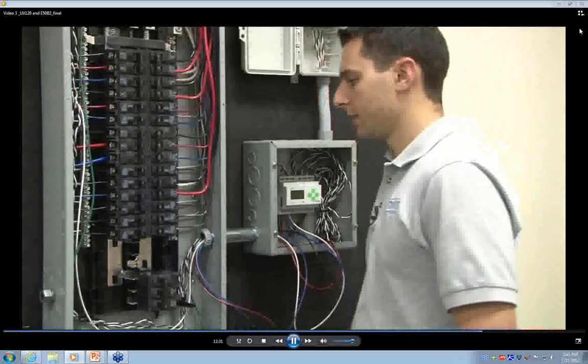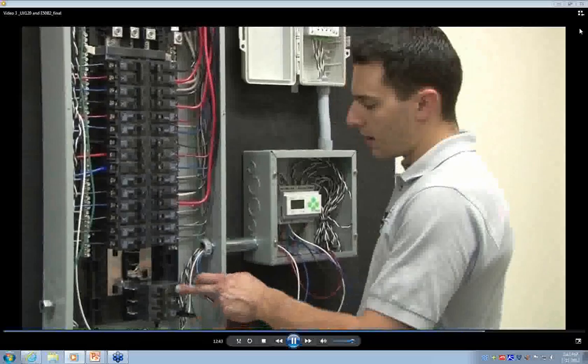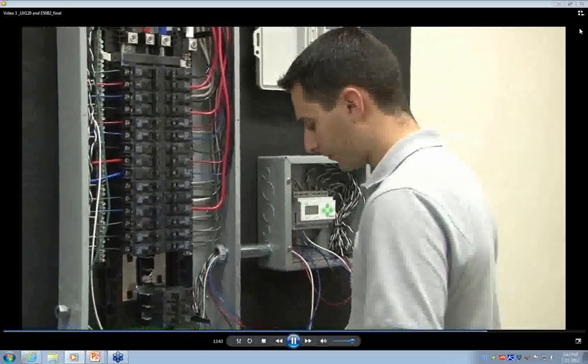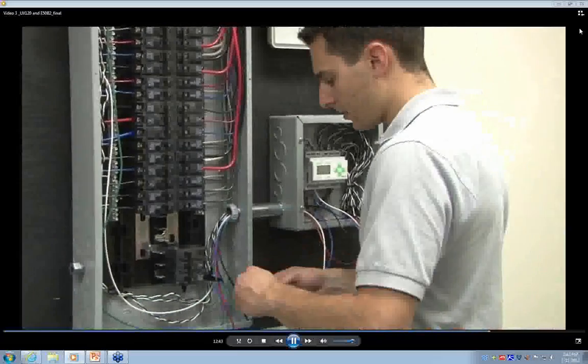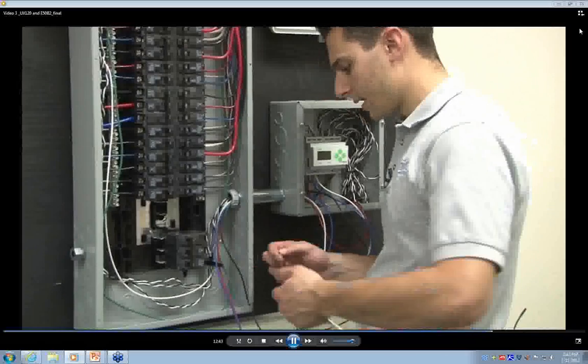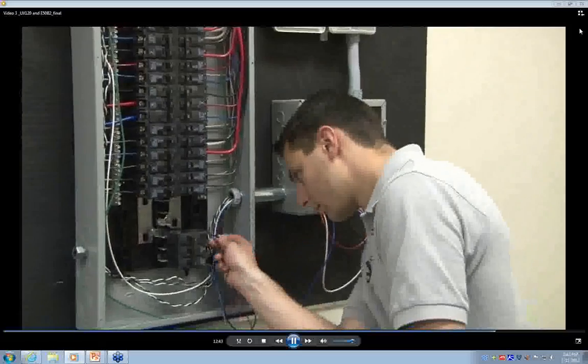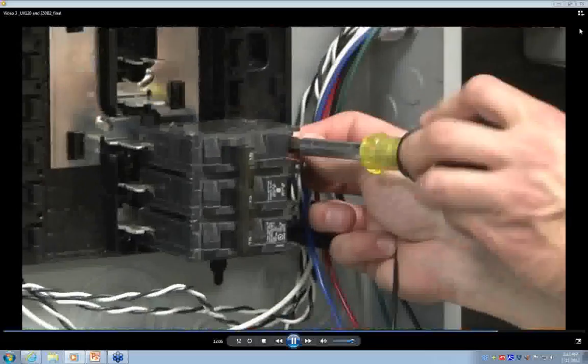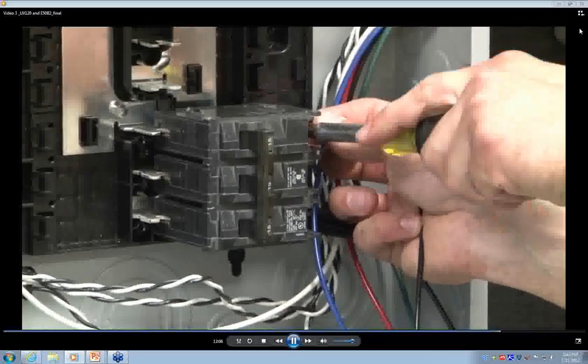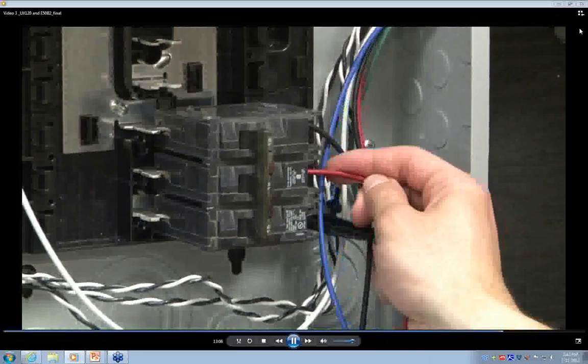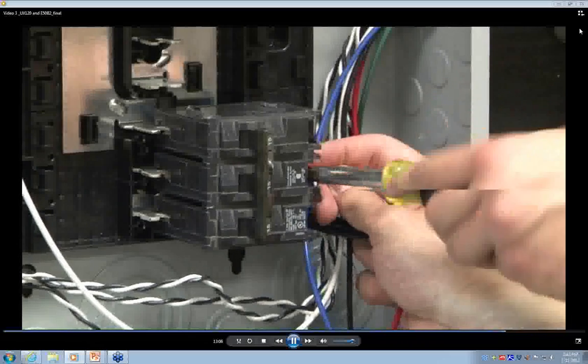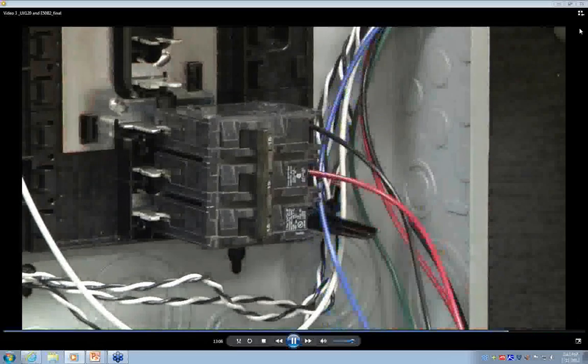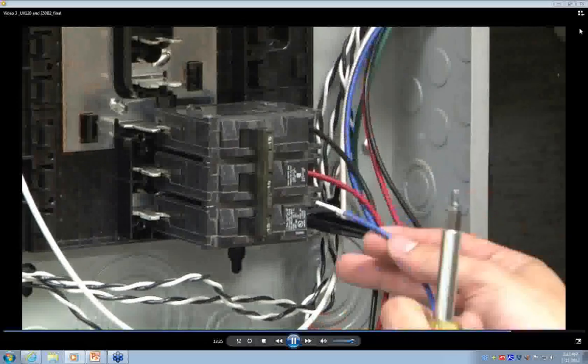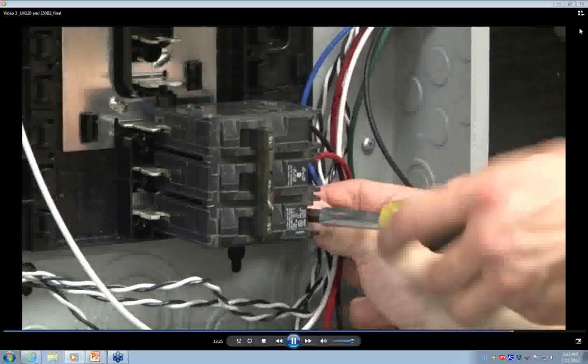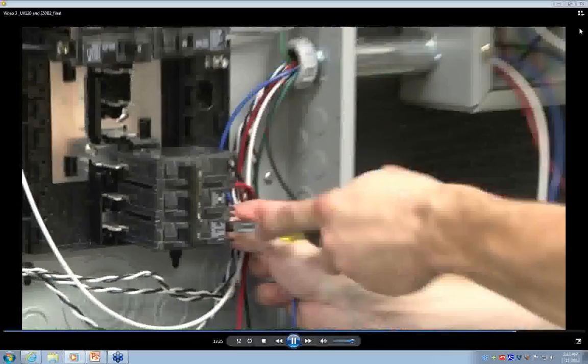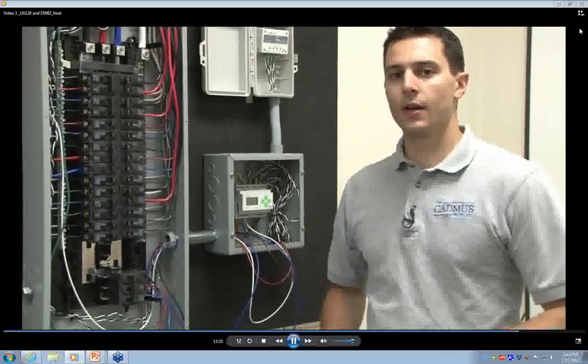It's also important that the breaker phases line up with the panel. In this panel, we have phase A at the top of the breaker, followed by phase B and phase C. We'll connect the black conductor to phase A. The red conductor to phase B. And the blue conductor to phase C. Since this is a permanent installation, we can now organize our conductors.